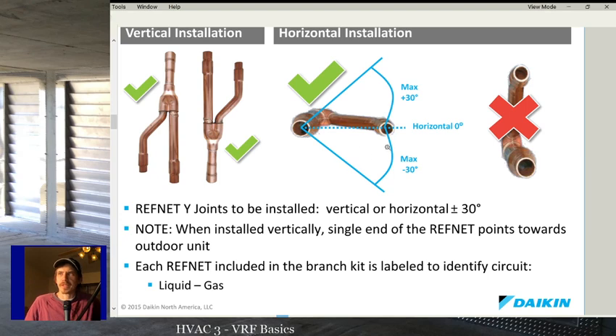And if you're trying to split a line, because they even have mini splits now where you can split the line set as if it's VRF, when you're doing systems like that where you're splitting line sets, you should think about, okay, what happens when I split the line set this way? Is it going to be an efficient way to split the line? Learn to think about the turbulence in the line, and think about the refrigerant pipe as ductwork in this case. How is the turbulence in the line going to affect how the refrigerant's flowing through the pipe?